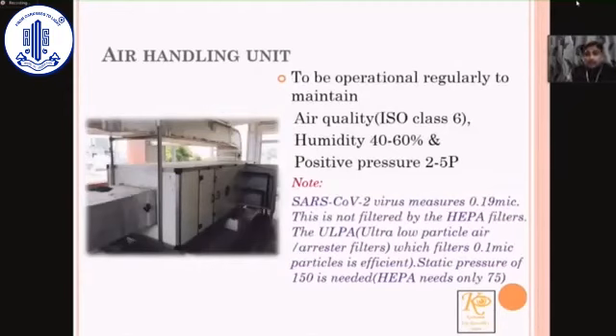The air handling unit is the most important thing. Cleaning the air handling unit and the pre-filters has to be done as per the hospital protocol. Ideally, they should be done once every month.